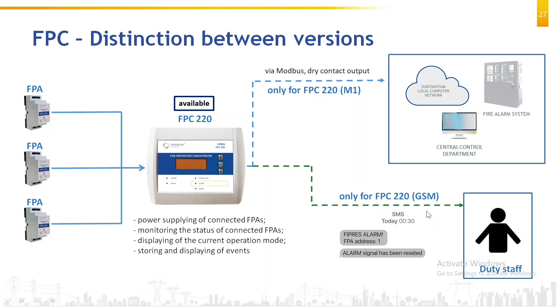Okay. Now, what is an FPC? FPC configuration we will see. FPC is designed to receive signals from FPA, monitor the status of communication lines, register and display the values. FPC comes in 3 varieties: FPC 220, FPC 220 M1, and FPC 220 GSM. FPC 220 can only display the values. FPC 220 M1 can display and communicate to the remote PC. FPC 220 GSM can display and send an SMS to a designated mobile number. So these are the 3 varieties of FPC: only display, remote communication, SMS.